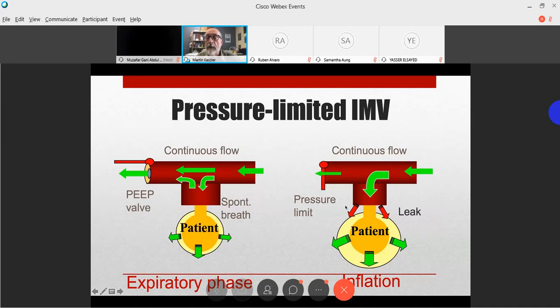And we're not worried about any large leak around the endotracheal tube because there's plenty of fresh gas available to maintain pressure within the circuit. Any excess flow overflows over the pressure limiting valve. And this works, of course, very nicely, except for the problem that once compliance changes, the volume delivered to the patient's lungs will change at any given pressure.